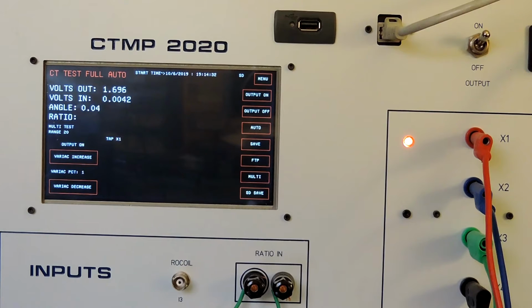I could be landing the leads after I measured the previous CT, or doing a winding resistance test on another CT, or having a coffee break, or going to lunch, or whatever I want to do, because the test set will test the CT fully automatically. Now doing the X1 tap, 2005 on that tap, says 2000.12.